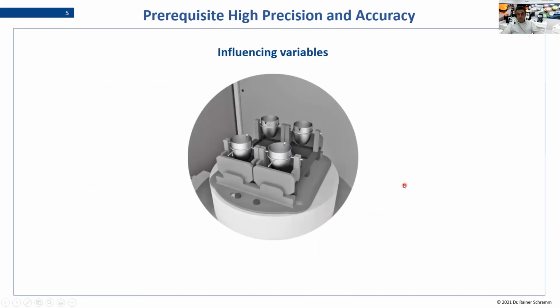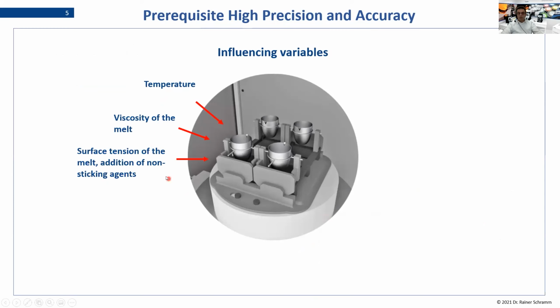But to get high homogeneity, we need to look at all the variables which influence our system. A very important one is temperature. The temperature influences the viscosity of our melt. There's also the surface tension of the melt. Some elements reduce the tension, and then you use non-wetting agents so that the melt goes back and does not stick too much to the wall of your platinum ware. The fusion time is very important, especially if we are looking at volatile components like sulfur or halogens. Temperature and time then become very important, because they influence how volatile your components are and how much you lose during the fusion. Only if you can keep both very constant is it no problem, for example, to analyze chlorine in fusion.